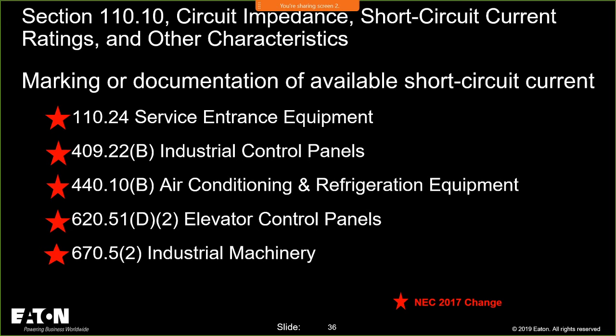This is my slide from the 2017 NEC. 110.24, we had that as changing because, although it had a marking requirement, you were required in the 17 cycle to actually document how you got that information. So you were already required to mark the available short circuit current, but now you have to have documentation on how you come up with that information.